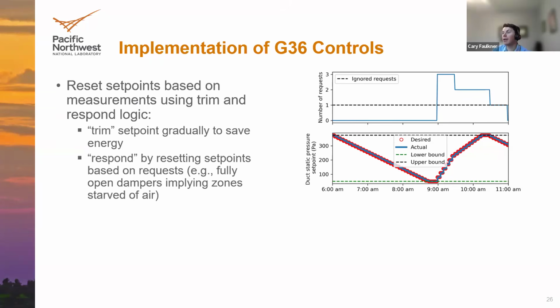And then when requests occur, in particular, the more requests that you have, the more dramatically the set point is going to respond. You'll see with 3 requests compared to 2 requests, the increase in the set point is a little bit more. There's also some number of ignored requests, where at one request, that request is ignored and you continue to trim the set point, but that's perhaps a tunable parameter.